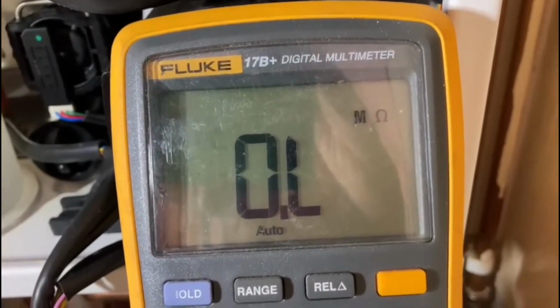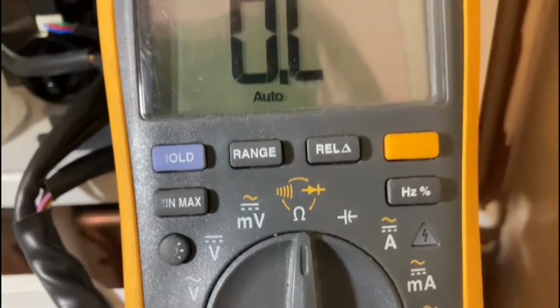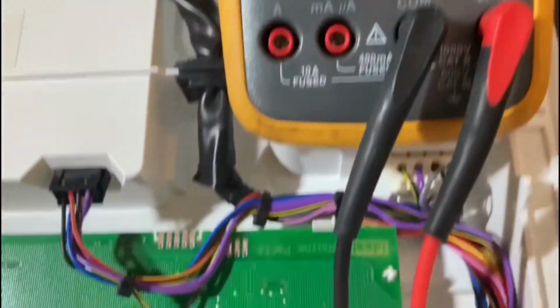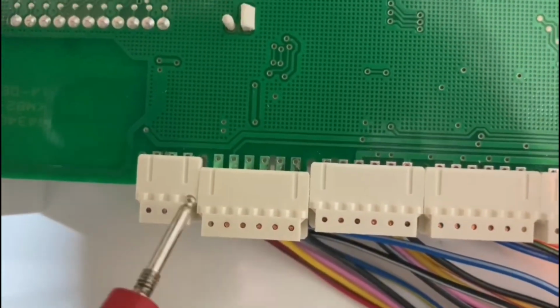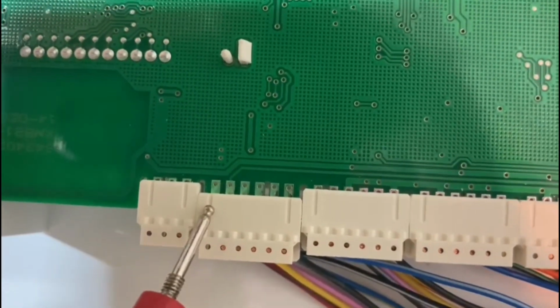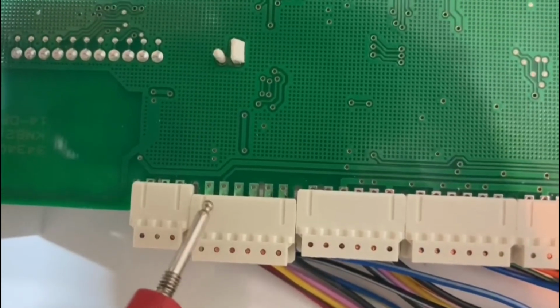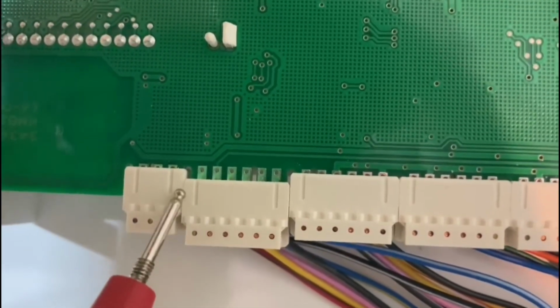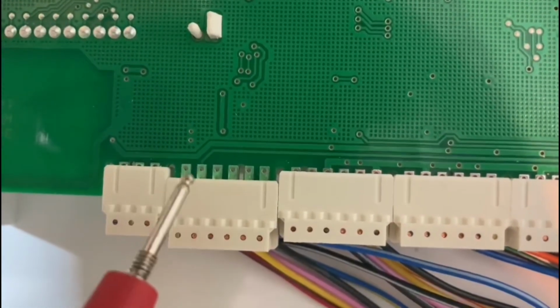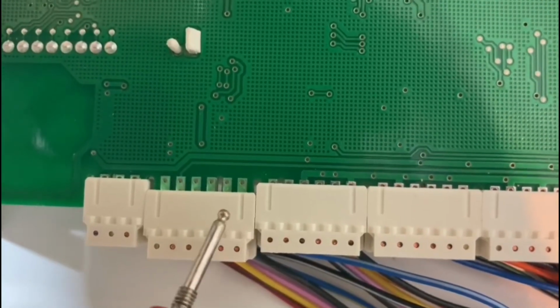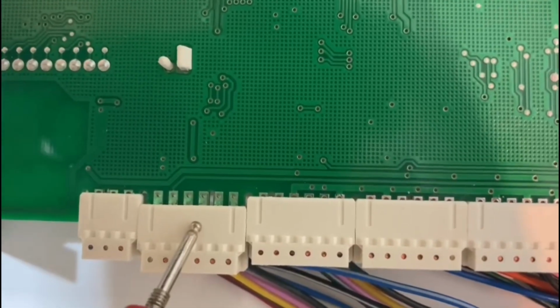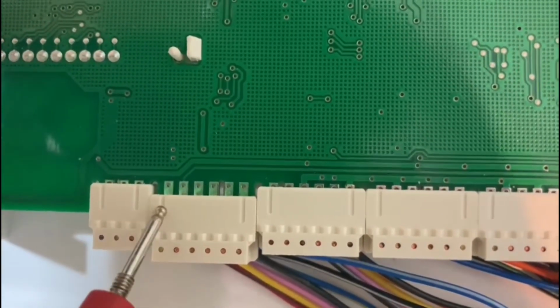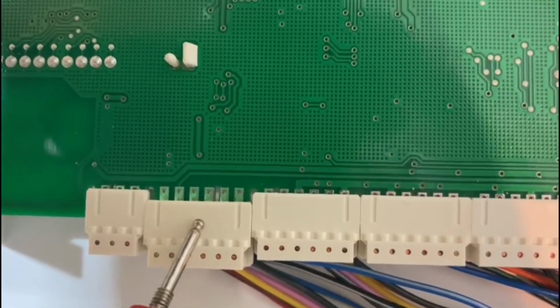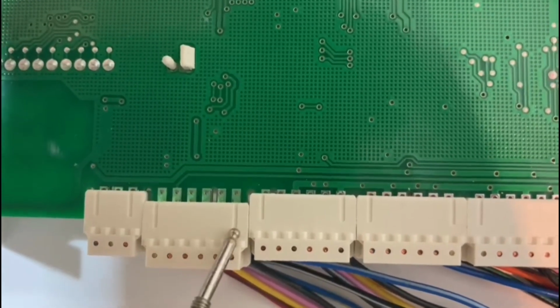This is the one with 6 connections. My multimeter is set to ohms, and I'm going to show you how to test the coils. I'll show you the first 2 connections. These 2 here are the power connections to the motor, both 24-volt supply. This left connection supplies these 2 here, and the right connection supplies the far 2. So if we test single connections on the coil, we'd go from this one to any of these 2, and then from this one to any of the far 2.